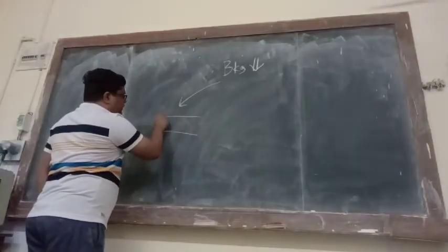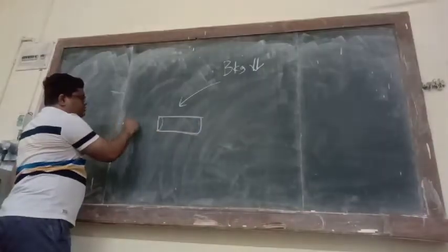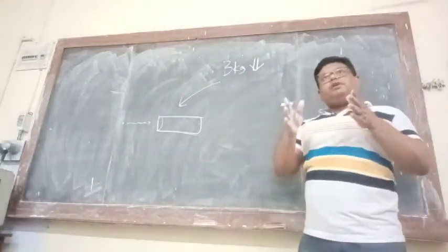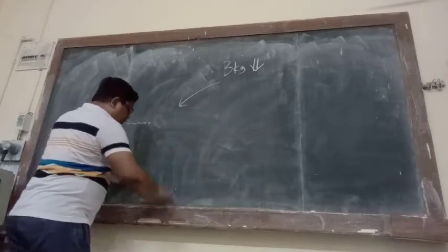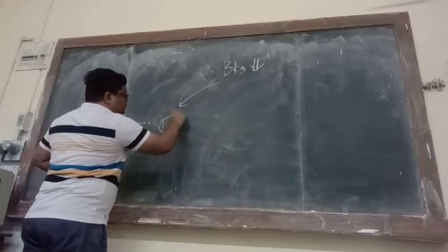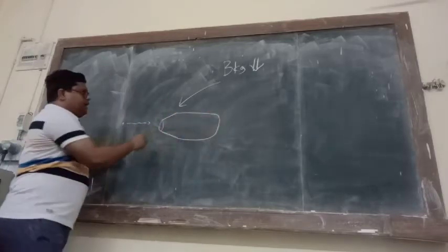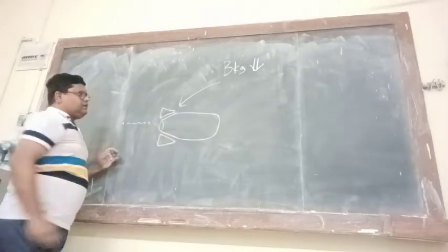A cylindrical detector, something like this. And this is the source, the gamma ray is coming. Now, this technique is called tapering of the front part of the detector. That means the front part of the detector will be like this, something like this. So I am getting rid of the material in this part, which is ineffective.